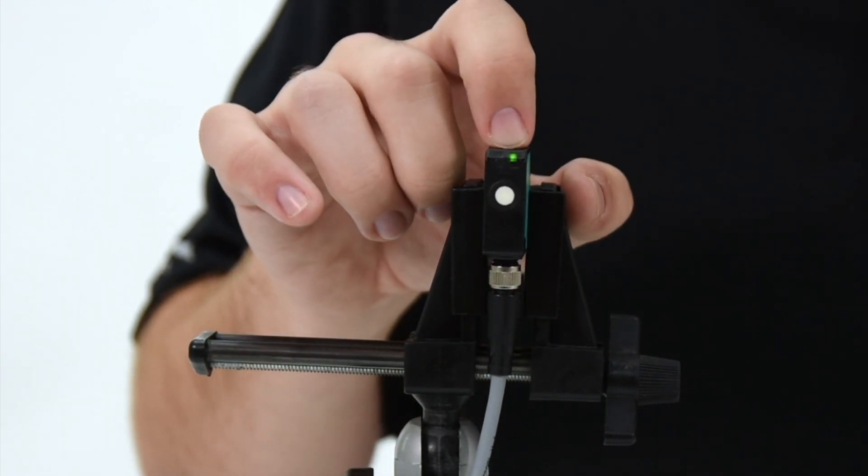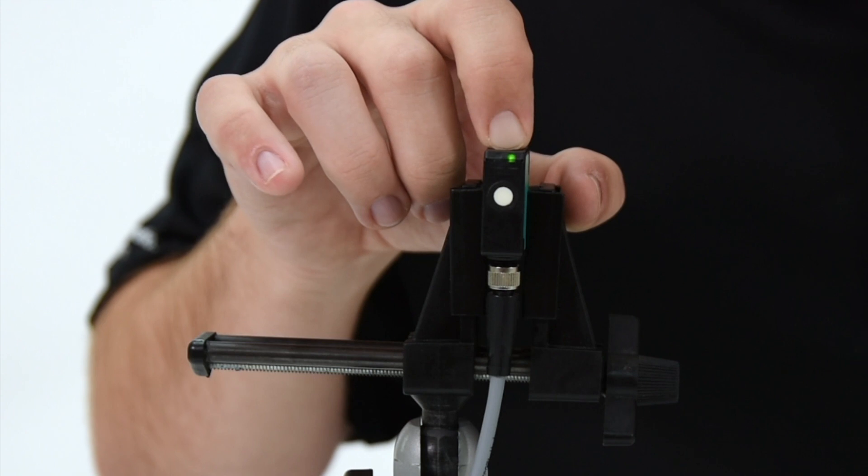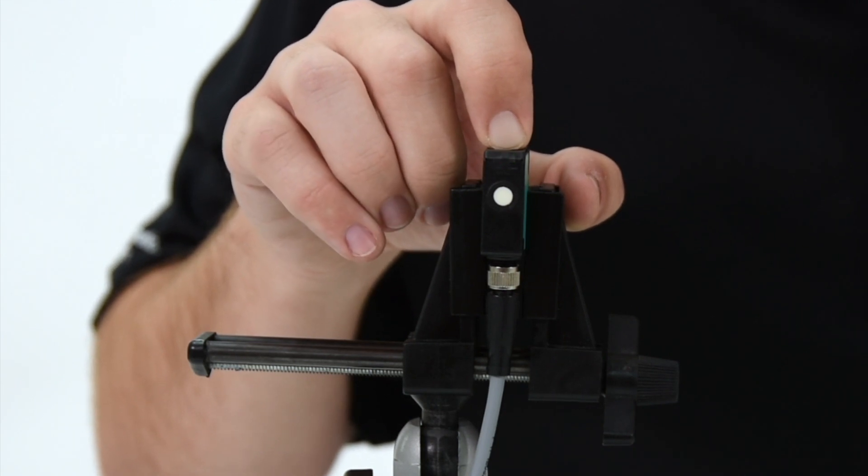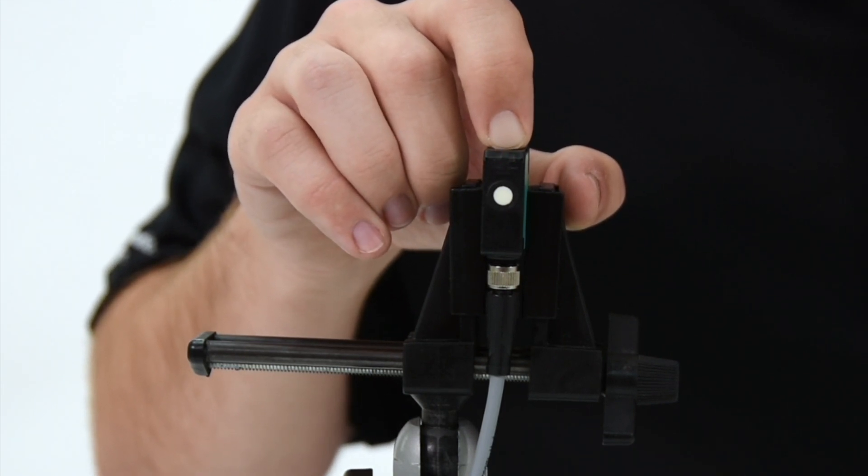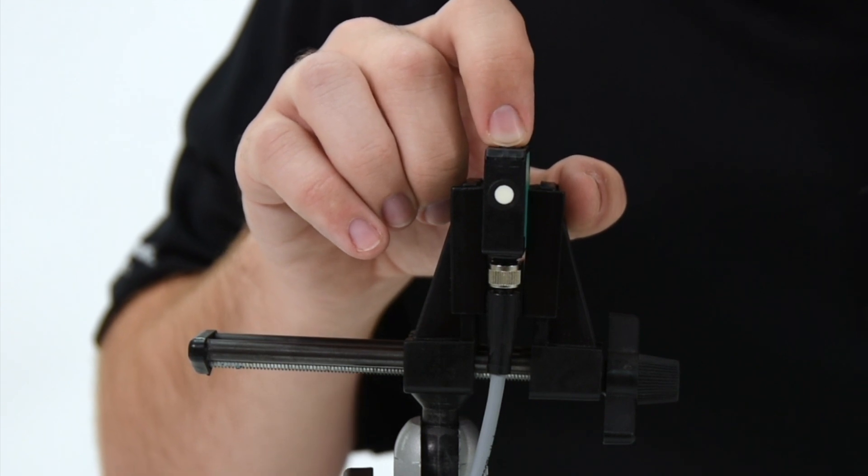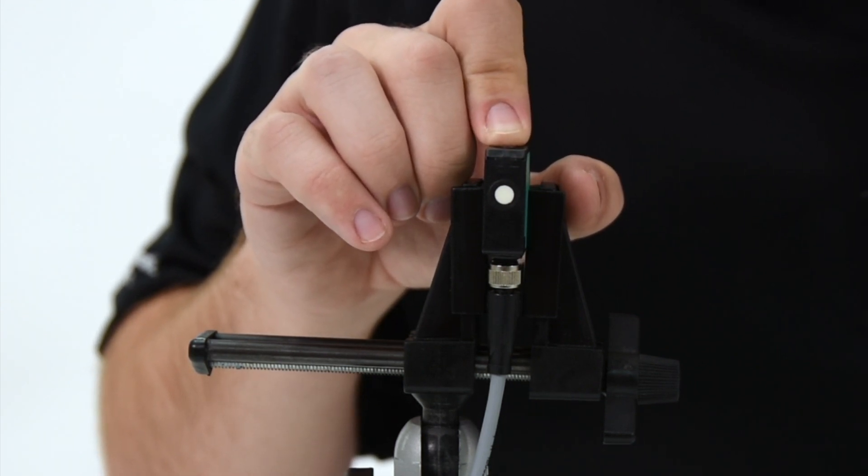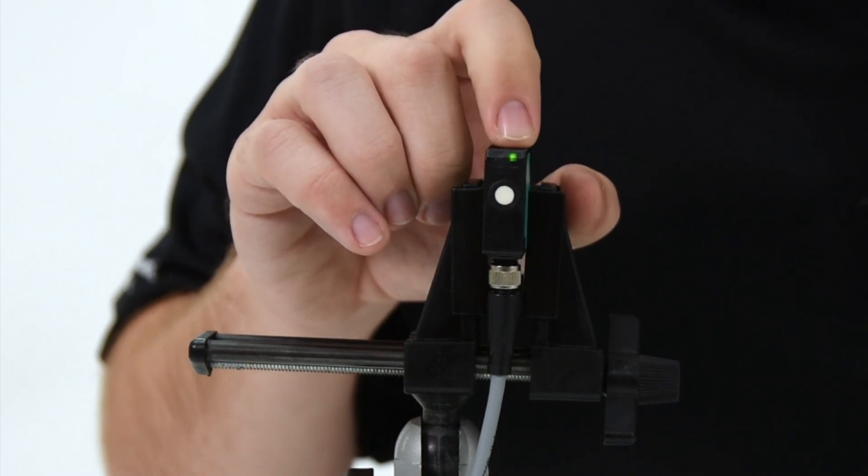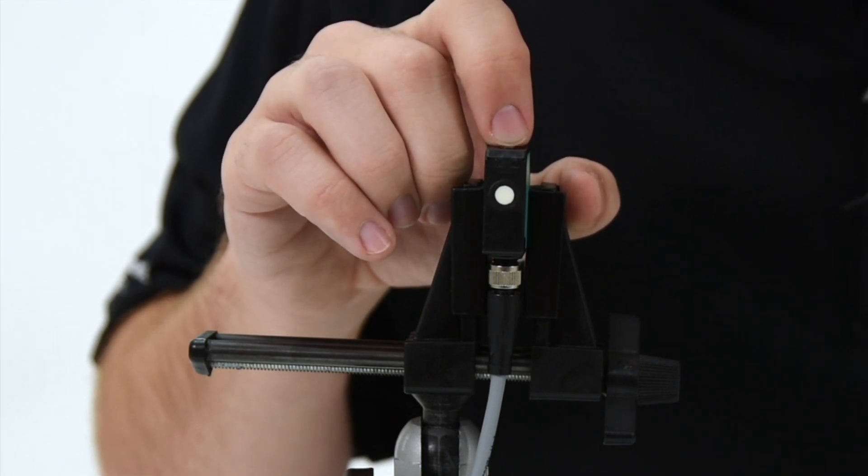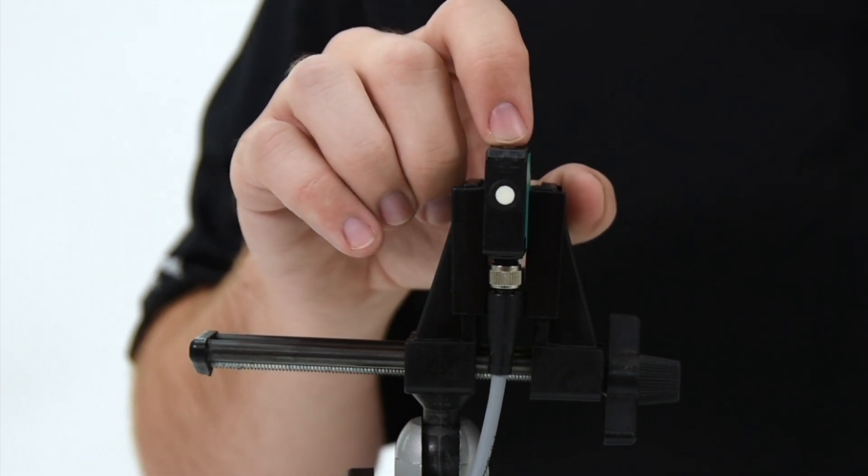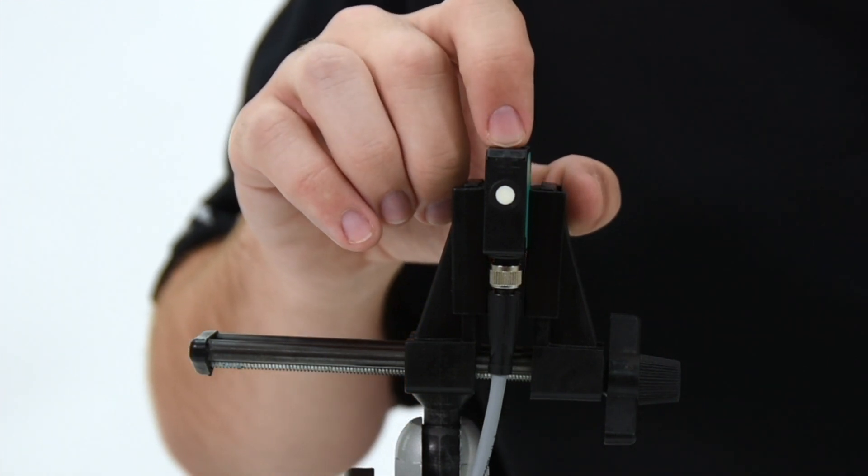Now to begin programming, we will hold the button for approximately 5 seconds. You will see it flash orange, and then once it begins to flash green, we are ready to begin. So now that it is flashing green, we are setting the switching mode for this sensor. Flashing three times indicates that we are in hysteresis mode.